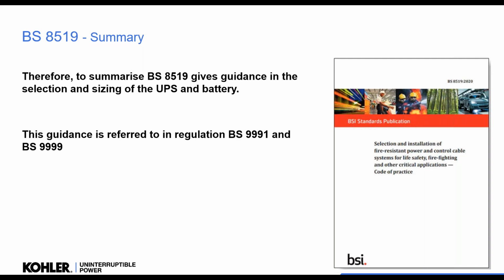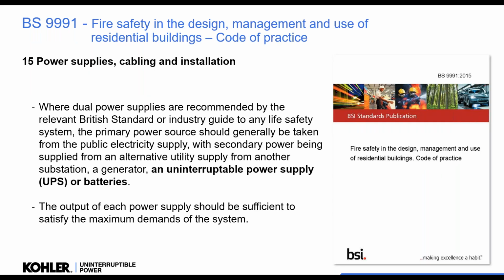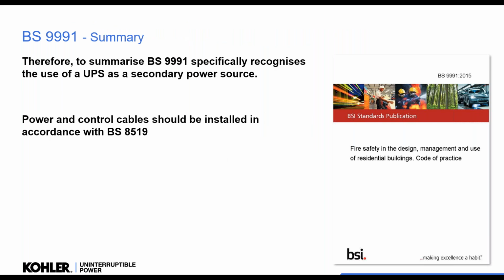So 9991, for the power supplies, cable and installation of UPSs, does talk about where dual supplies are recommended by the standards. The primary supply should generally be taken from the public electricity supply, and the secondary from a generator or an uninterruptible power supply, or battery. So it specifically says you can use a UPS as a secondary source, and it must have sufficient capacity to supply the required load. Okay, so quite clear.